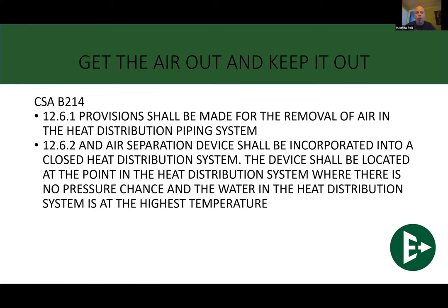Again, super important point: CSA B214, code reference 12.6.1, provision shall be made to get rid of the air inside of a distribution piping system. And 12.6.2, an air separation device shall be incorporated into a closed loop heat system. You don't have an option anymore. You have to have an air separator in there. I see people try to save some dough by not putting in an air separator, just that high point air removal. You really don't have that as an option. You've got to use the high efficiency air separator.